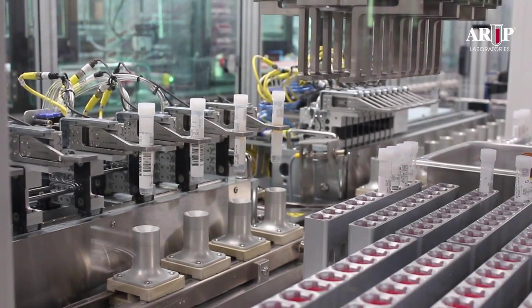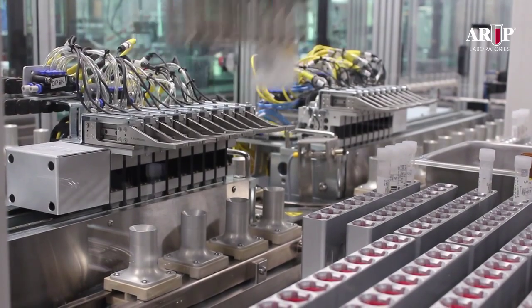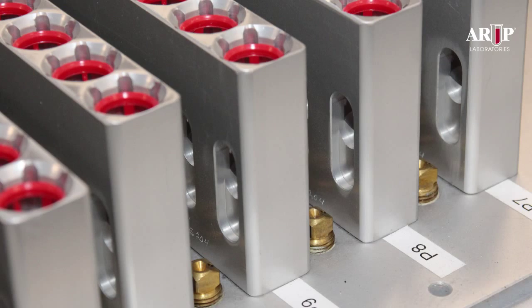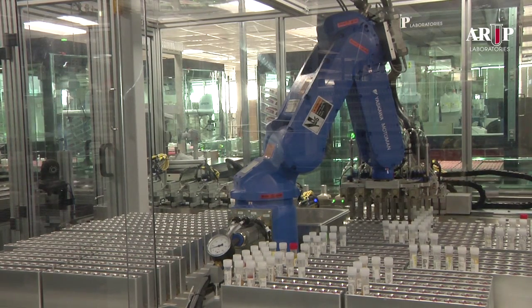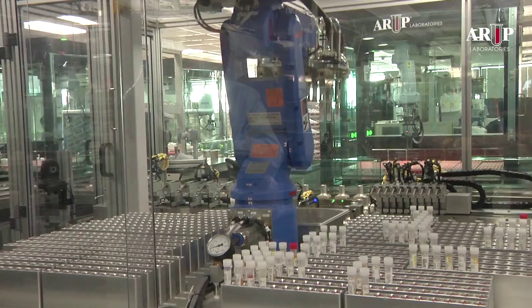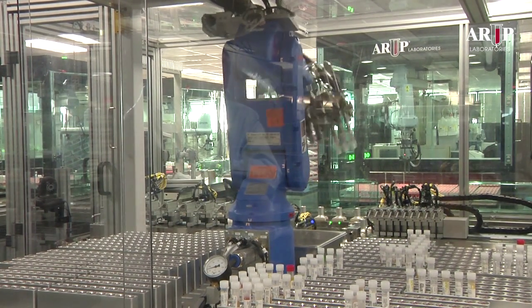This robot places the tubes in aluminum fixtures on the deck of the TMW. There is a slit in the fixture in front of each tube through which a brass nozzle blows 2 liters of room temperature air per minute aimed directly at each tube. Regardless of the tube's size and the volume of the frozen serum or urine, each specimen is thawed in 25 minutes or less.